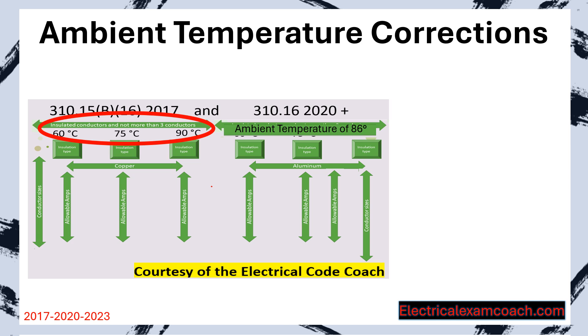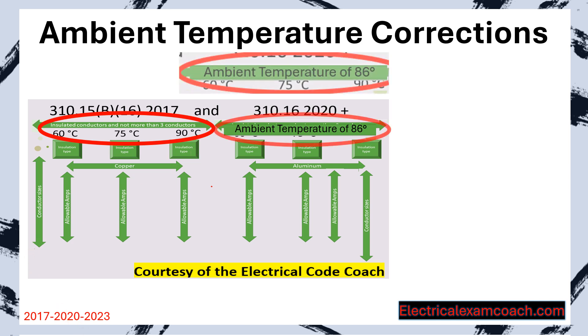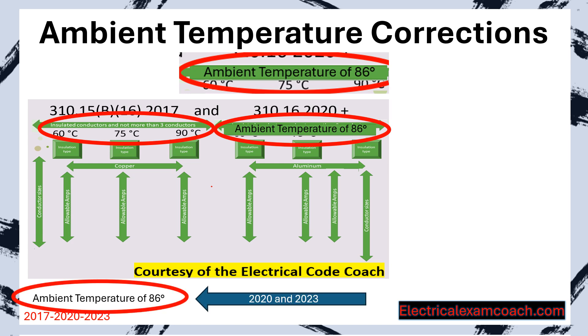Let's take another look at our primary ampacity table. In the last lesson, we learned about the first part of the note at the top of the table — that these values are true as long as you don't have more than three current-carrying conductors. There's a second piece: in the 2017 code it's at the top, and in the 2020 and 2023 it's at the bottom. It states these values are true as long as you're in an ambient temperature of 86 degrees Fahrenheit. Any time you get outside of that, you'll need to do an ambient temperature correction.